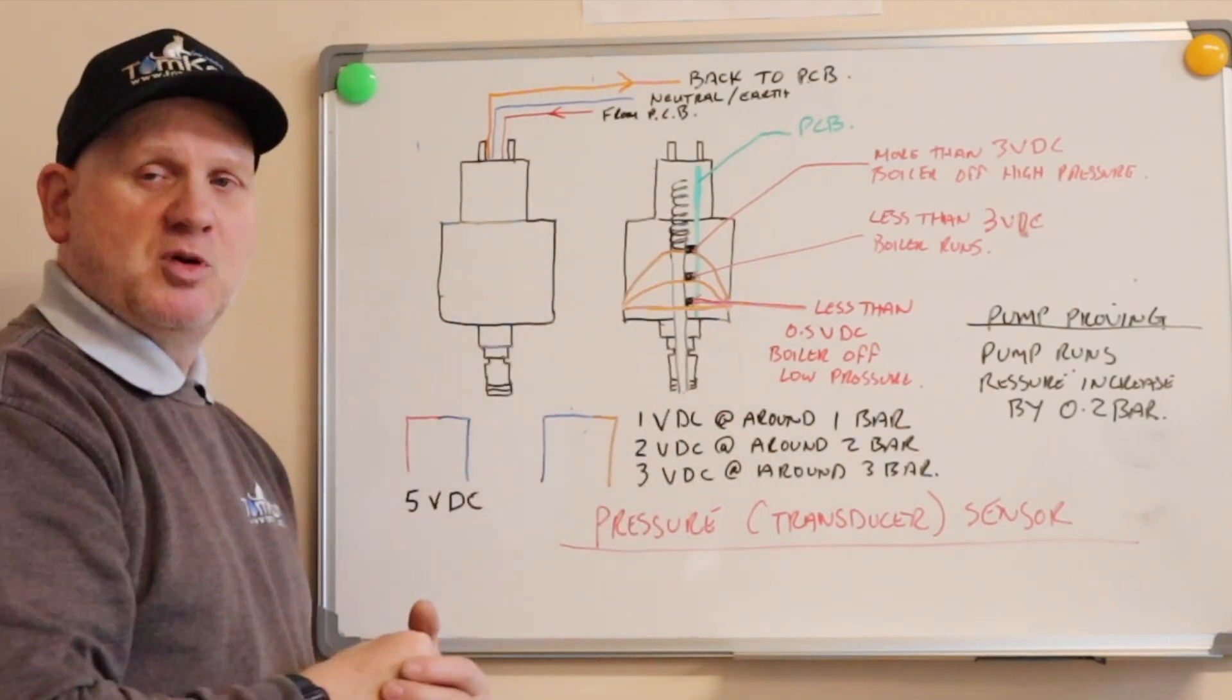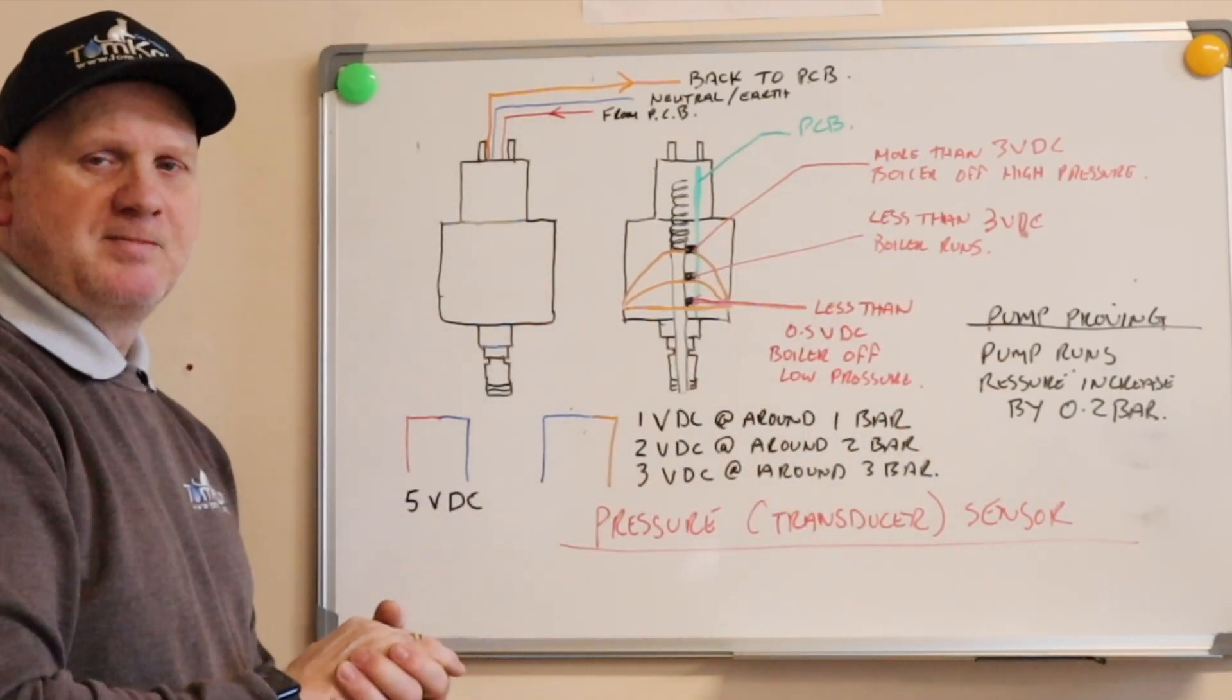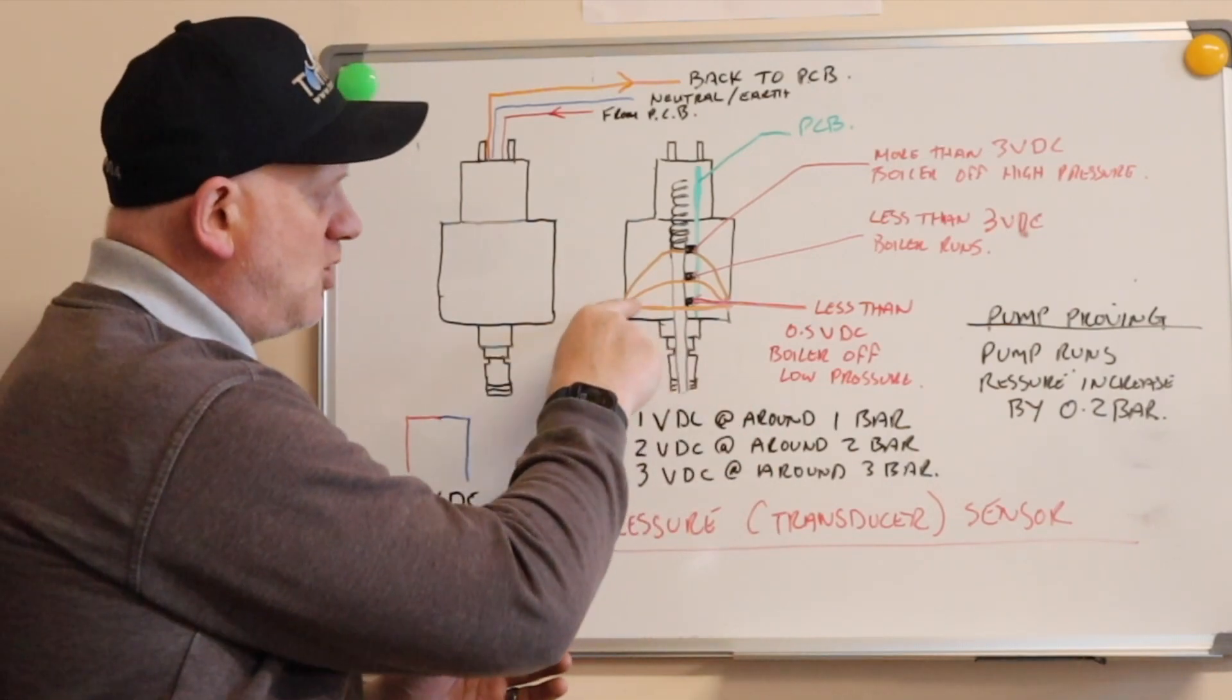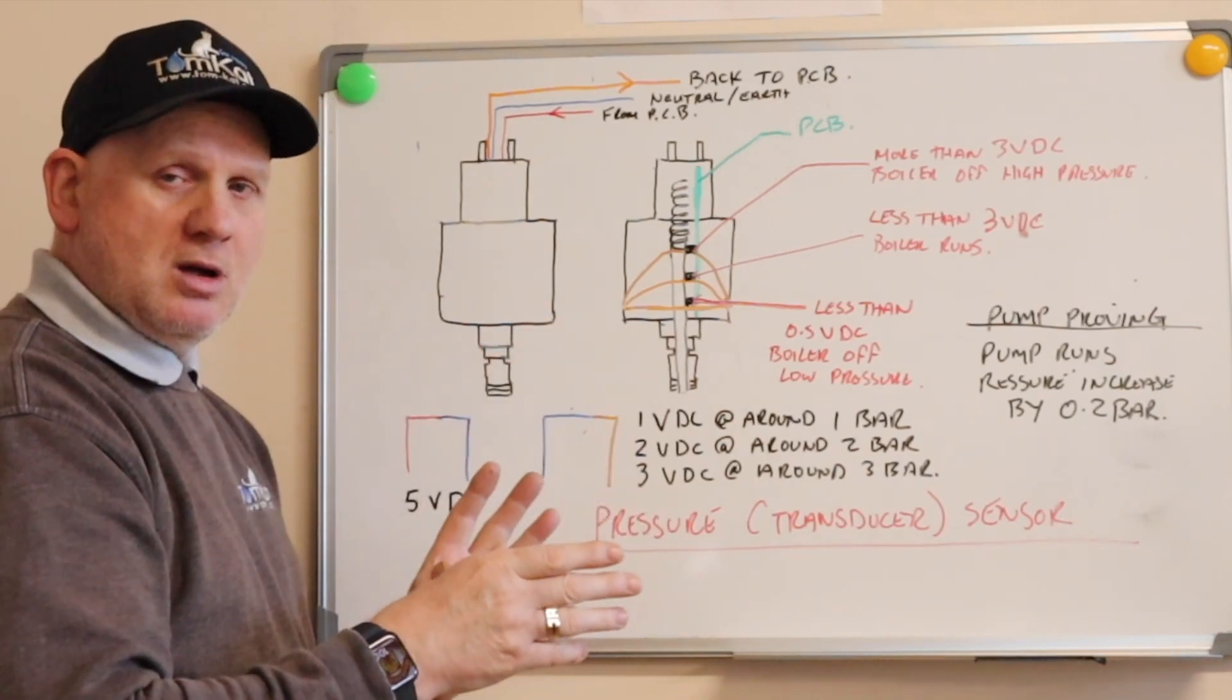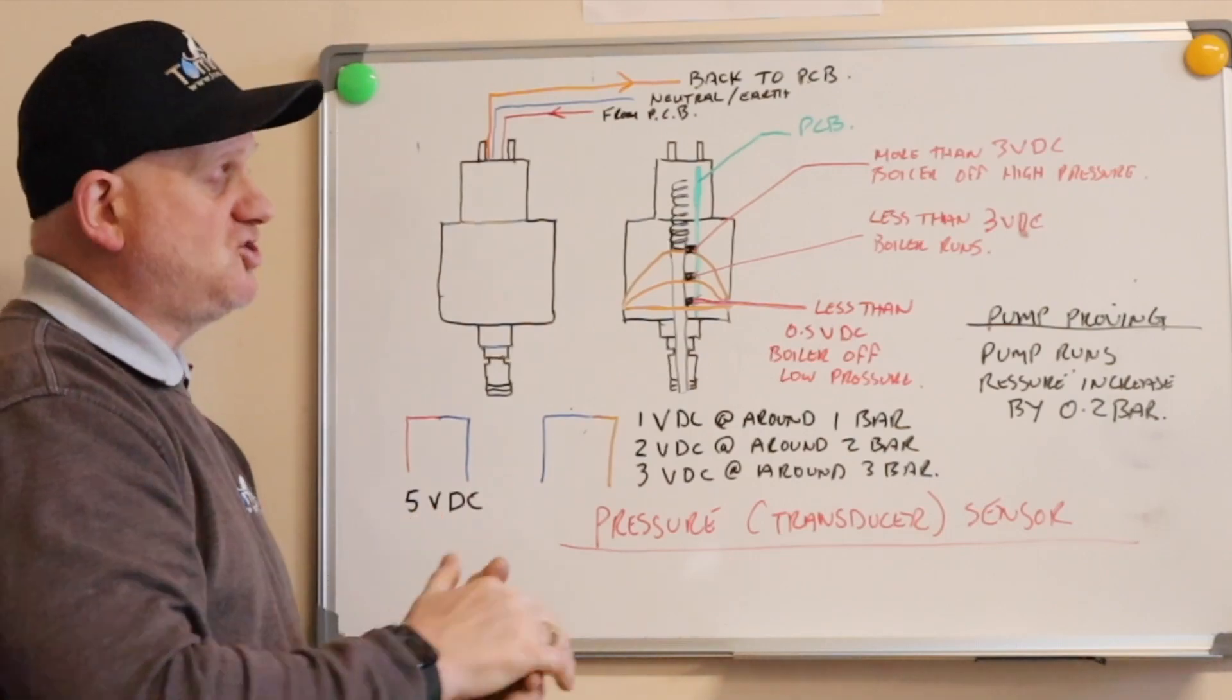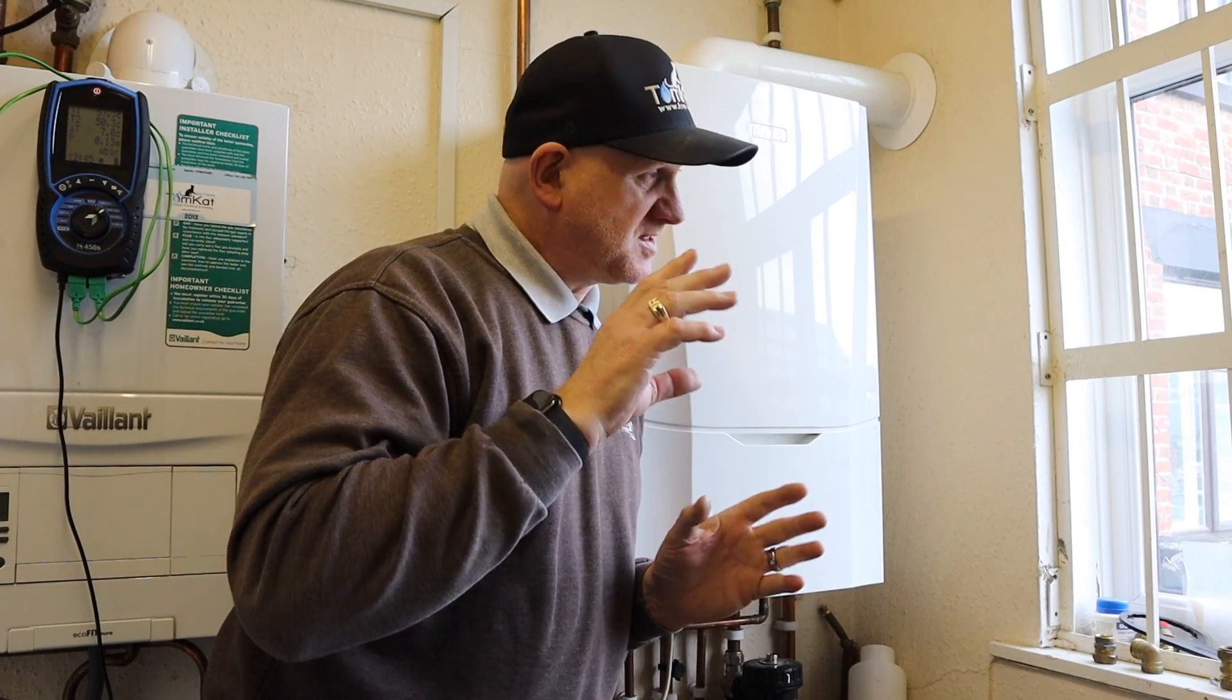Now the transducer can also do another job, which is the pump proving. So when the boiler turns the pump on first to see whether the pump's seized or there's any water in the system, it will move this little diaphragm by about 0.2 bar. And it'll know it's sending 5 volts DC, it gets about 0.2 volts coming back or a change. It knows there's water in the system and it knows the pump is working correctly.